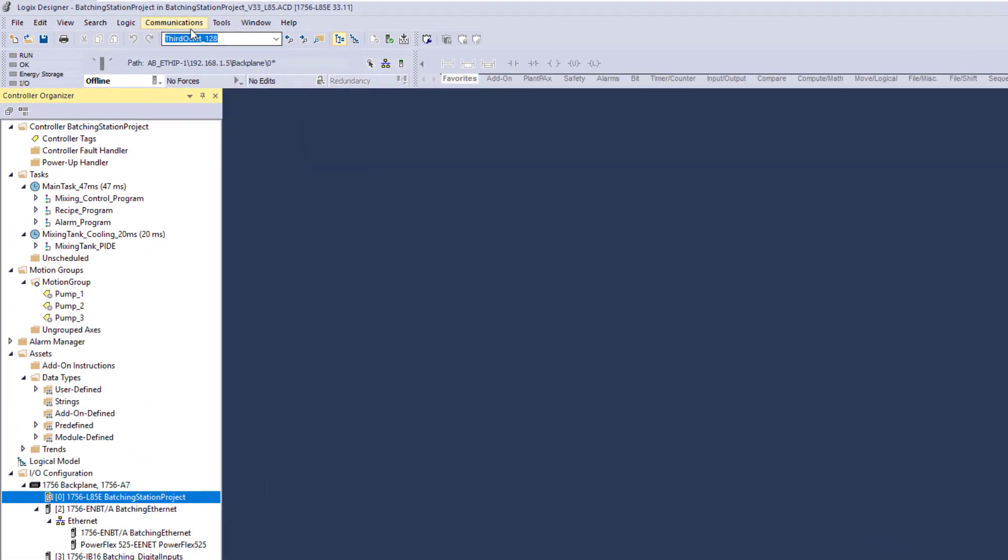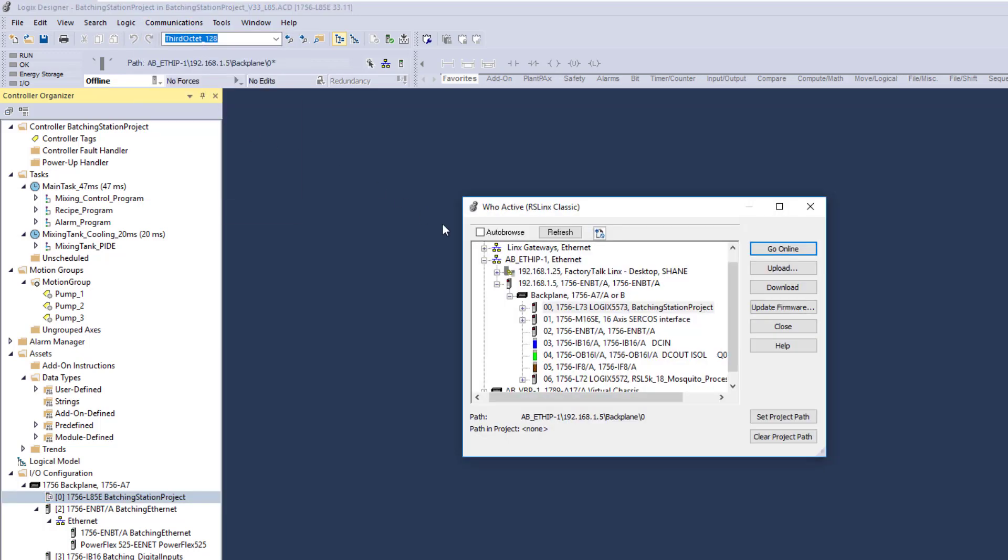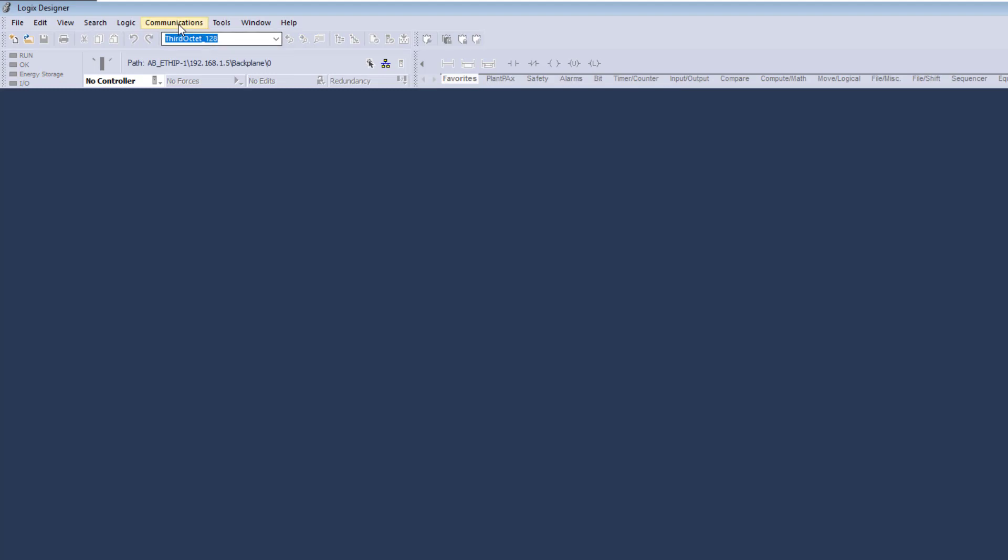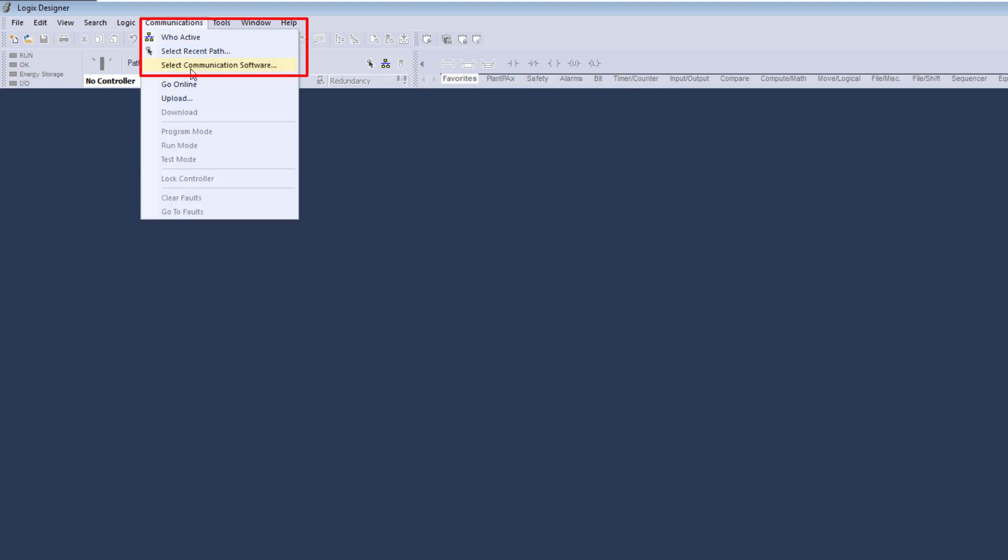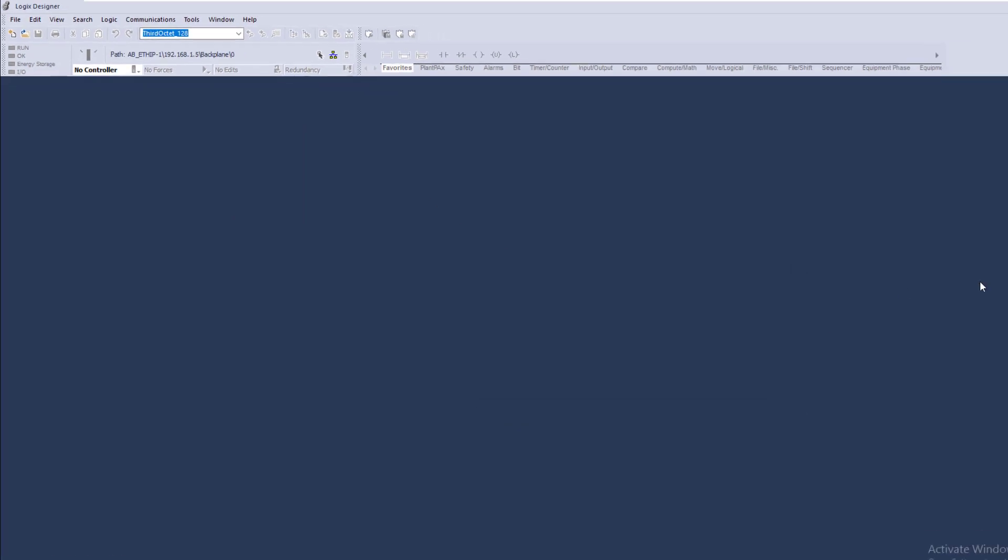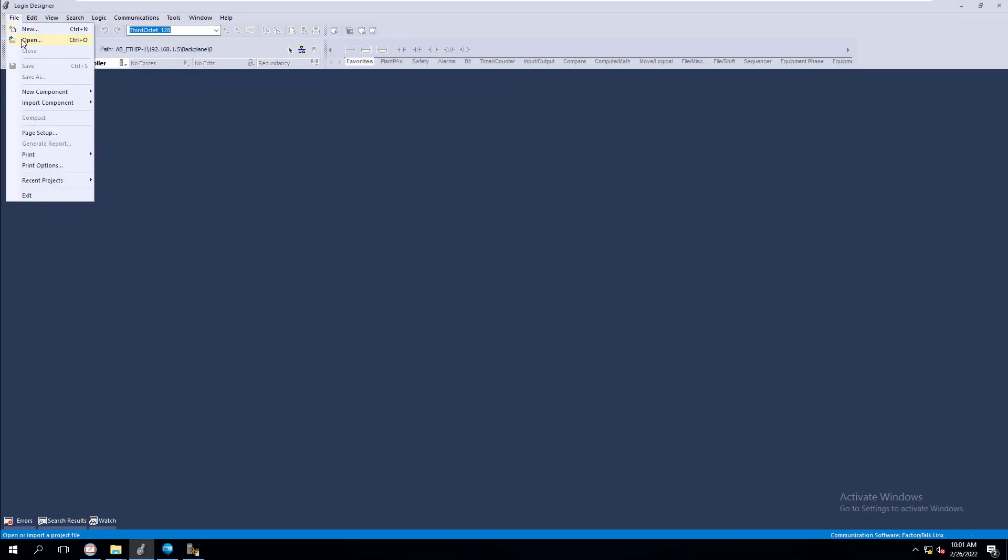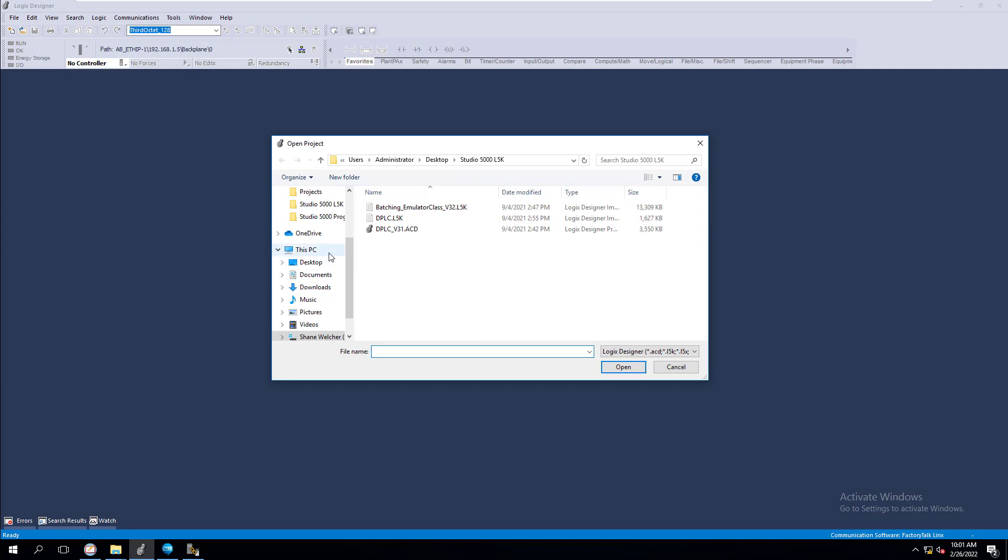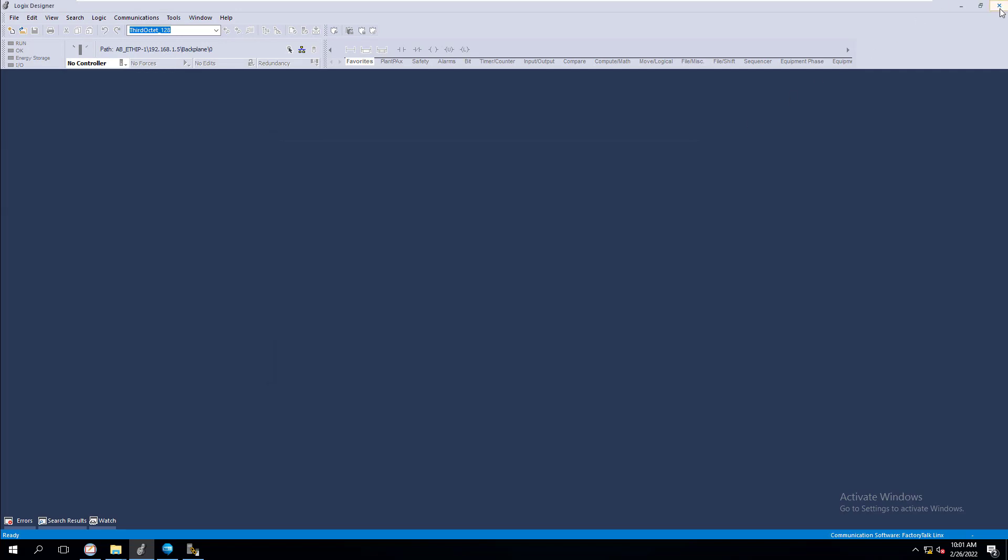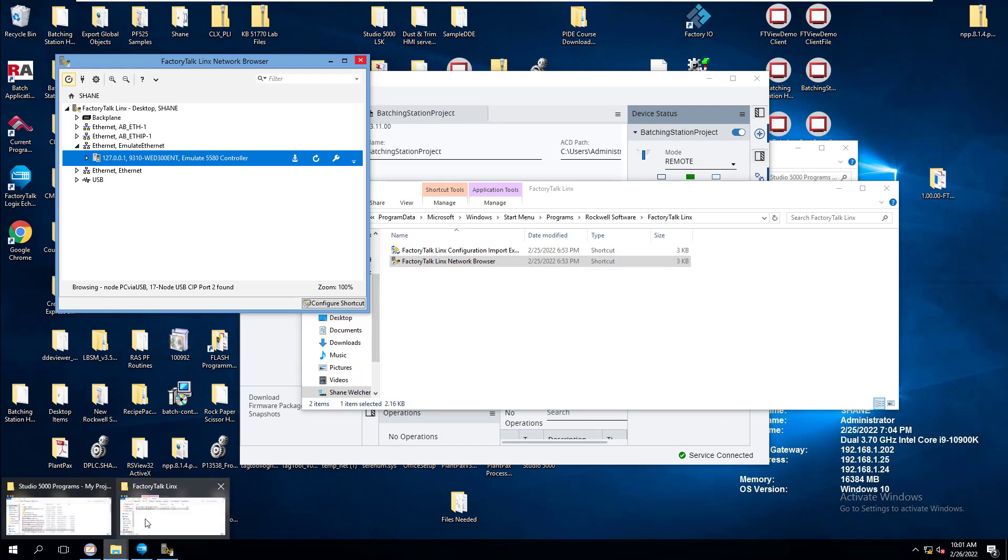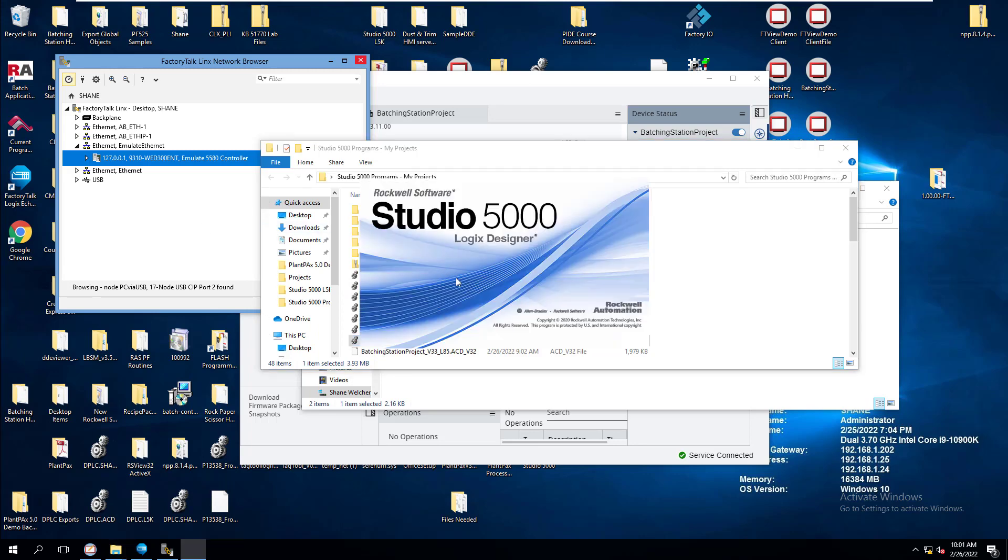So my project, theoretically, that I have open right now, I can go ahead and get online. But if I go WhoActive, I'm currently using the software of RSLinx Classic. So I can't go online with it. So how would I do that? I would go file. I would close. I'll come over here to communications. Then I would go to select communication software. Change that to FactoryTalk Linx. Hit OK. Then I'm going to come over here and open that back up. So I'm going to open up my file.